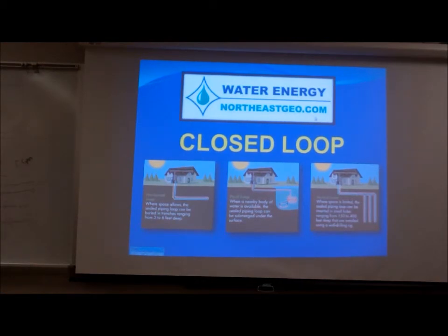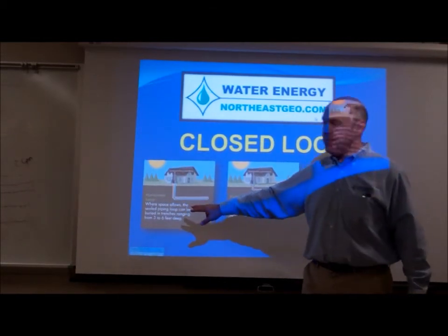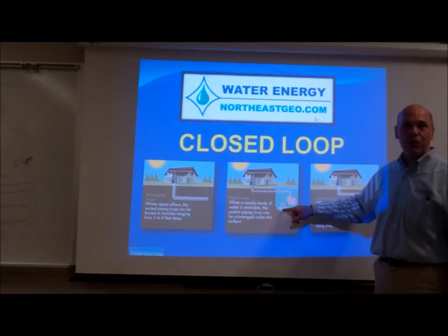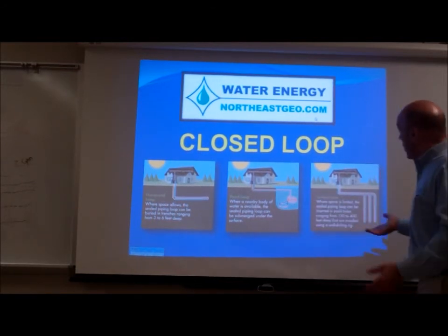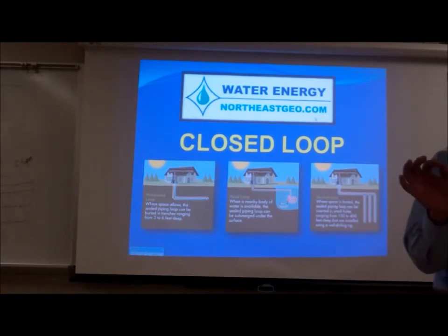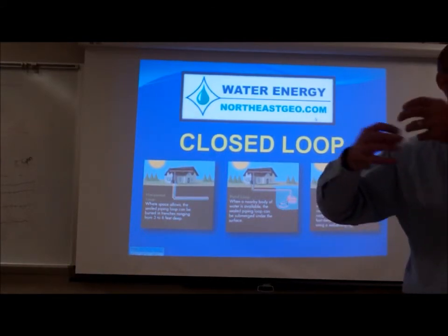The closed loop could be any number of things. Remember we talked about the amount of antifreeze, friction, and pumping. The horizontal loop — 4 to 6 feet down, 2 feet apart, out and back — I'm looking at about 700 feet of pipe per ton of equipment. Pond loop is about the same amount, but the problem is when it gets really cold in the winter, the outside of the pipe wall is at 50 degrees normally, but when the pond freezes over, it's going to be 39.5 degrees on the outside — so less effective exchange deltas. The slinky loop is another form of horizontal loop looking at between 900 and 1,100 feet of pipe per ton. So not only is your pipe investment higher, but so is your antifreeze investment and your friction — and so is your pumping penalty, because I've got more antifreeze to turbulate.